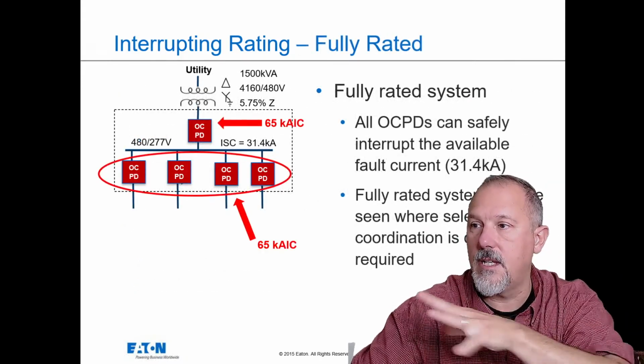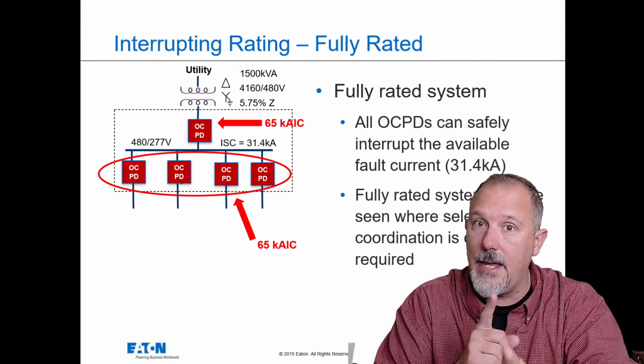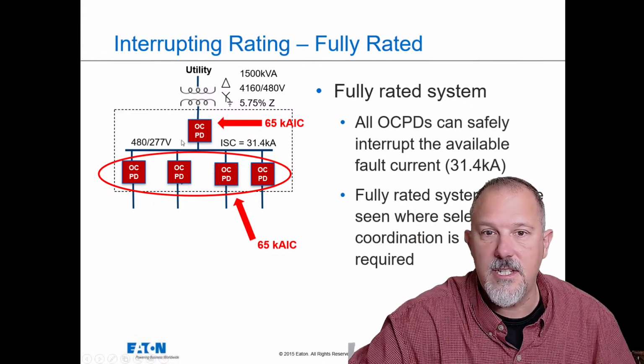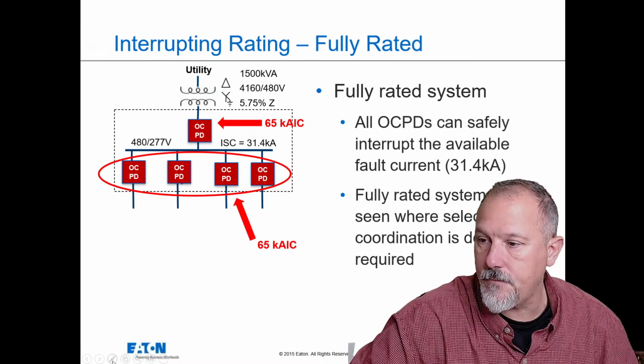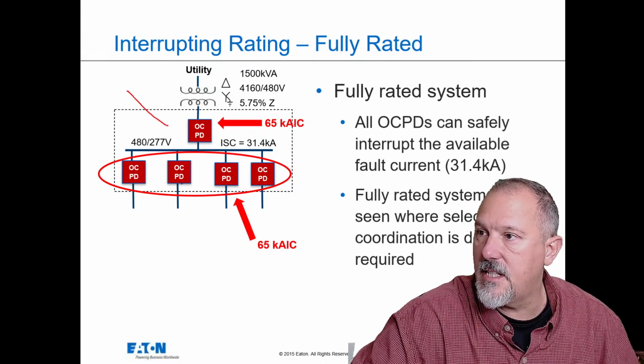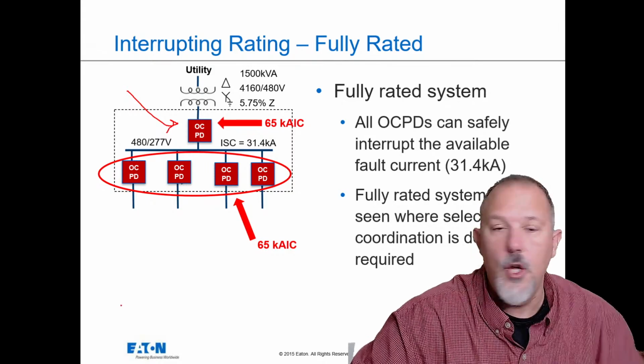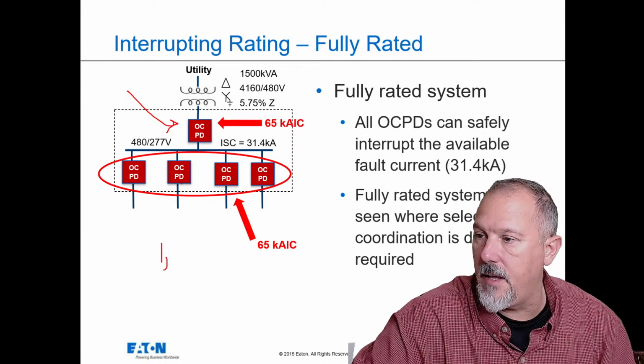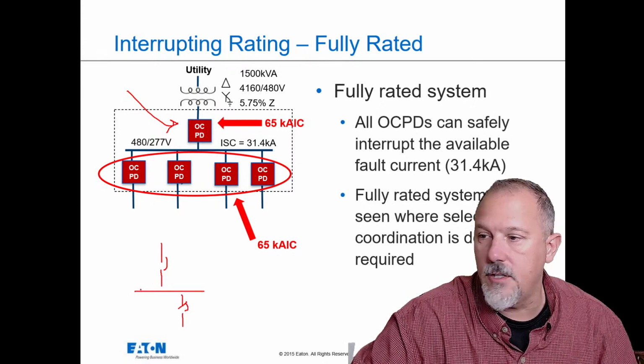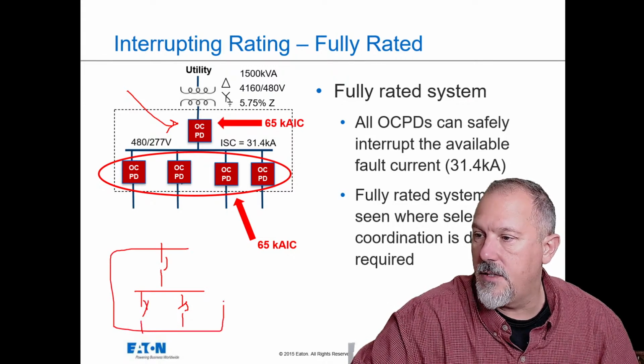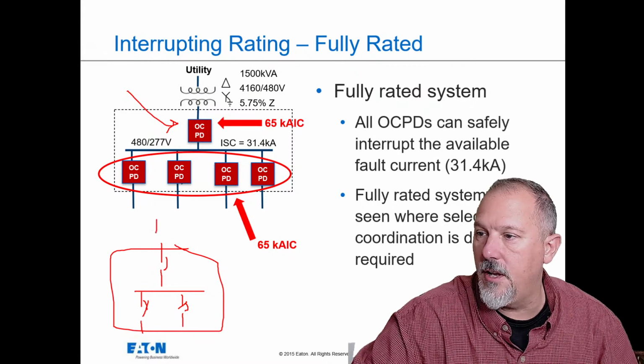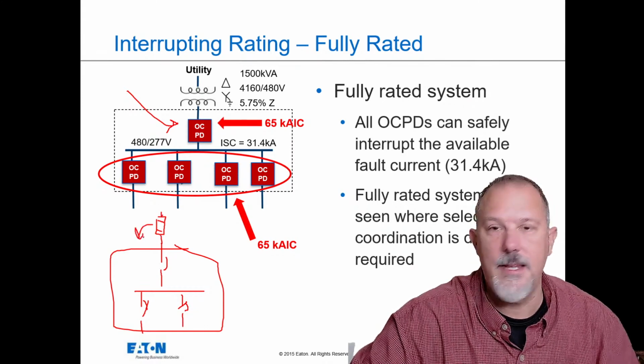Right. So we're talking this type of deal. But in your case, you probably have a whole panel board. So this 65K device right here, this is 65K, and what you're basically saying is I have a main breaker and I have branch breakers. Whoa, I can't draw like this at all. Look at that. Boy, that looks good, doesn't it? All of this is at 10K, and you want to put a fuse right here in front of this to say that this fuse protects that equipment.